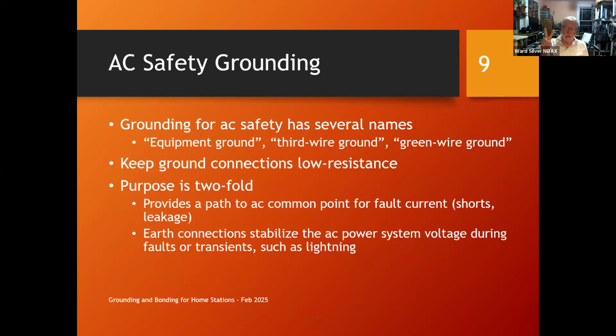There are two purposes to this ground wire, and only two. One is it provides a safe and controlled path back to your AC common point for fault current, shorts, and leakage current, as we just discussed. And all these earth connections, because your AC service, if you look at the box, there will be one big wire that goes to a ground electrode, whether that's a rod or a UFER ground or whatever.